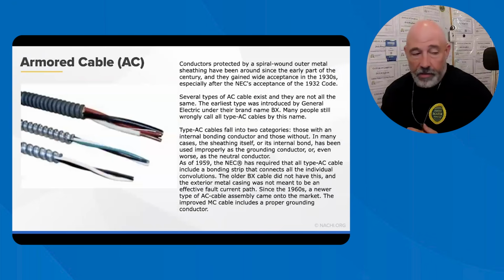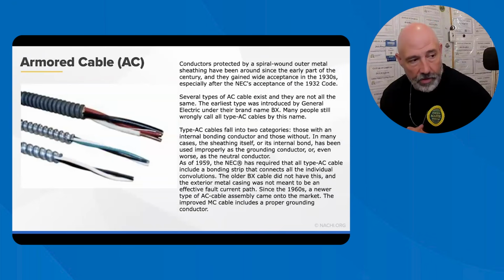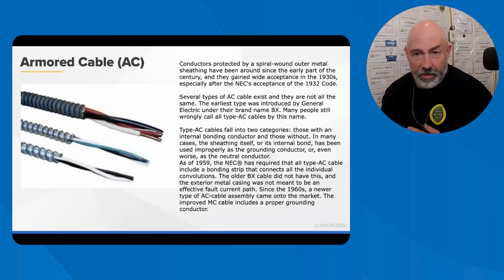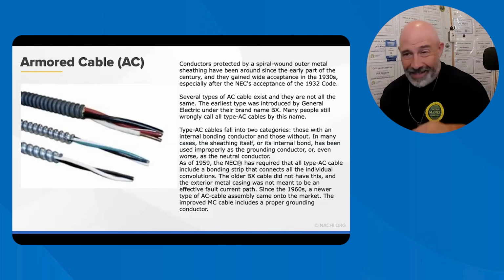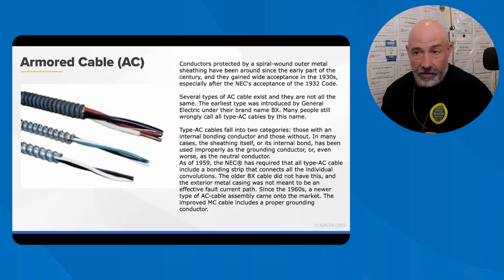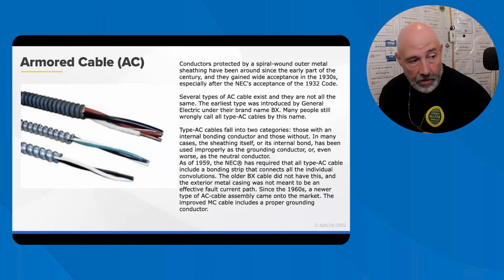So here are some more armored cables. I'm not going to go into too much detail here. The older cables lack a ground. Newer AC and MC cables include the ground with it. A lot of times you can use the outer shell as a ground, but you need the bonding clamps around there and make sure that you're following it around. So that's all I've got to say about that.